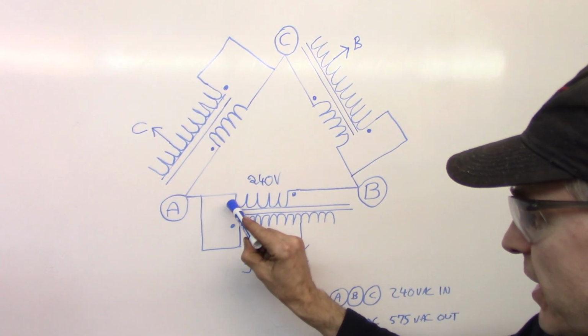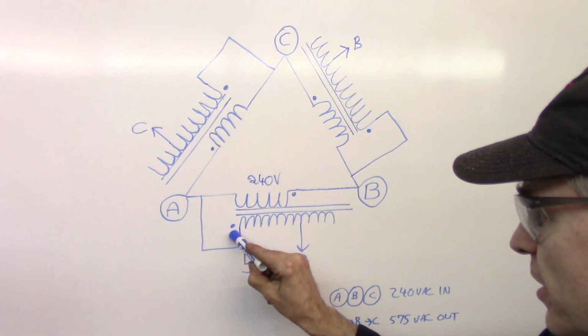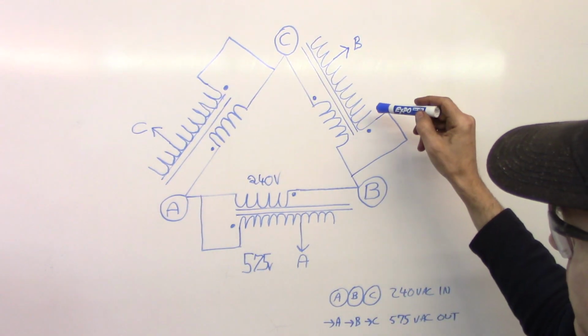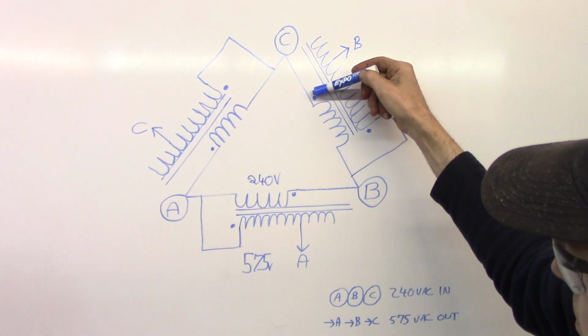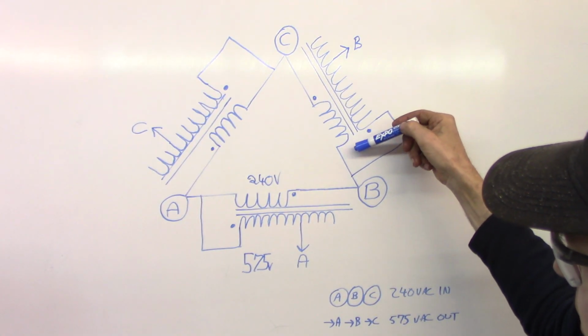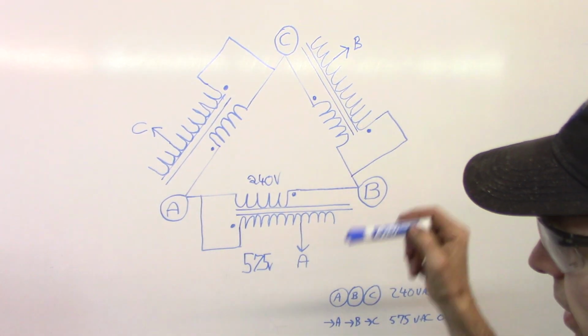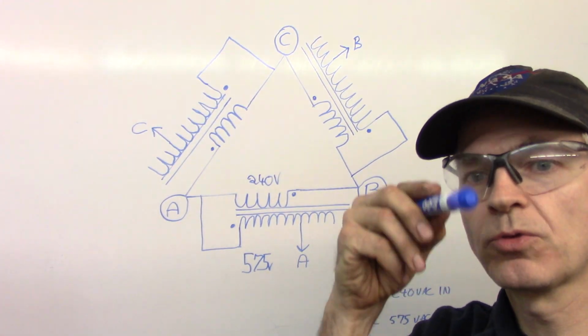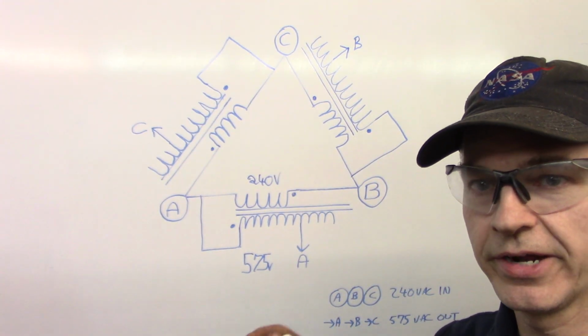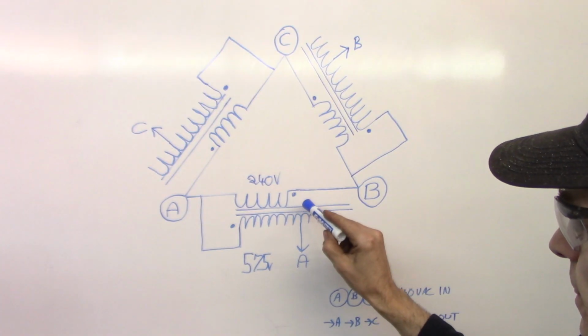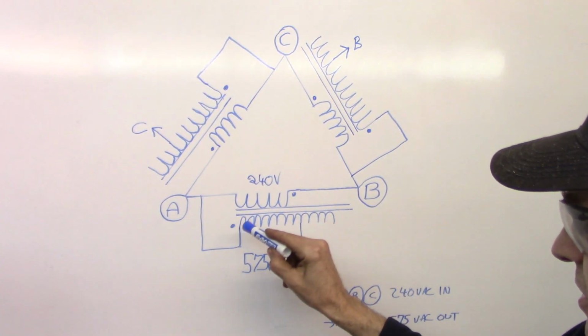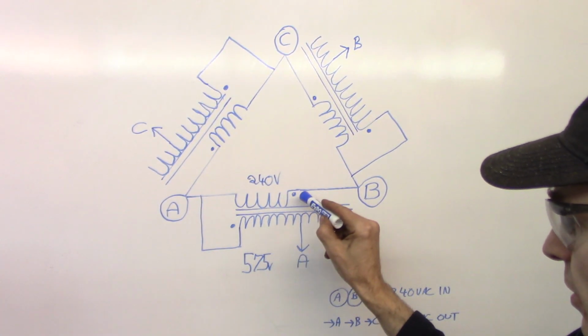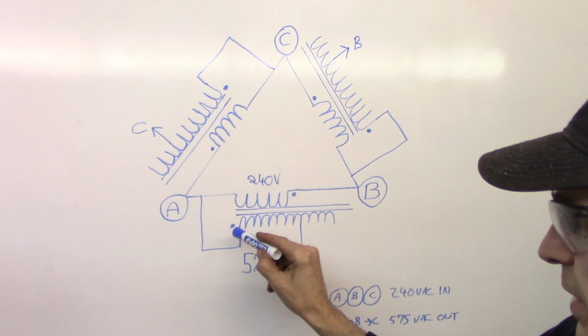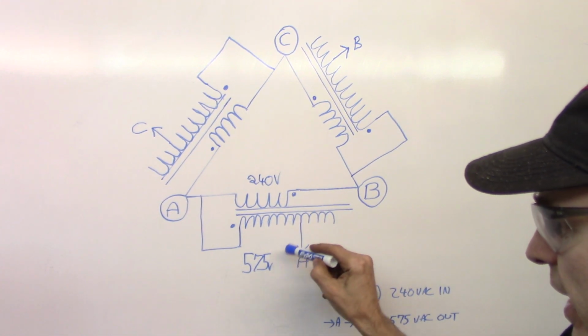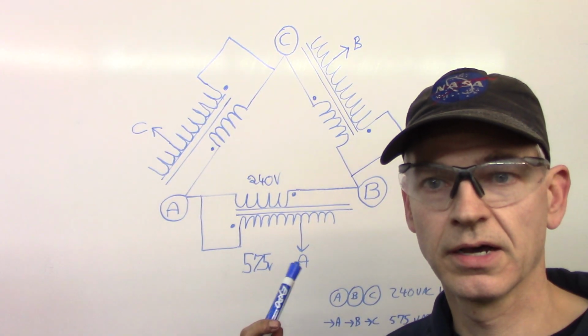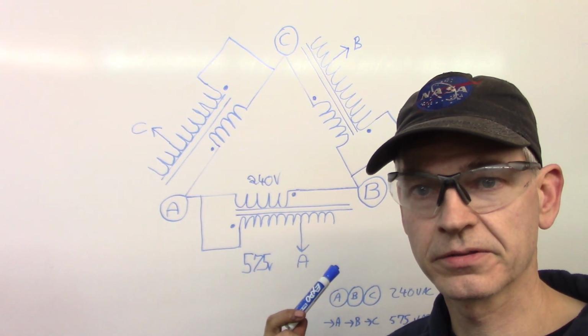What I'm doing is I'm connecting the end of one coil to the start of the other, right? I'm connecting start, end - I'm keeping the windings the same direction. If I went start to start, not end to start, that would be a bucking situation where I'd get less voltage reading out of the other side.